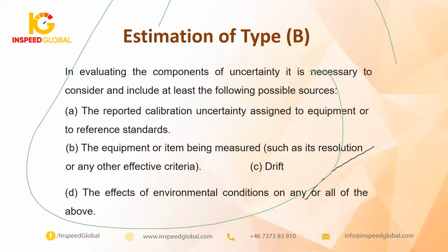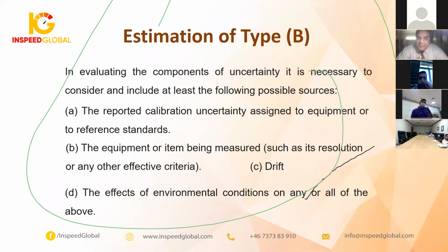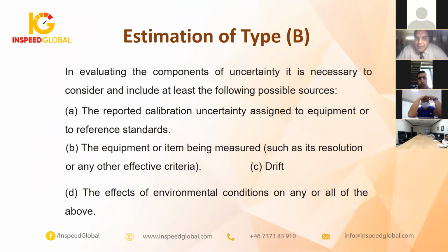Why? Because one of the requirements of an accredited calibration lab is to mention the uncertainty in the final certificate. It helps the testing lab, when receiving the calibration certificate, to get the uncertainty value directly from it. So the first value for type B is the uncertainty value which you mentioned already in your calibration certificate. Your lab will not do any effort for this point. You go directly to the calibration certificate to get the uncertainty.